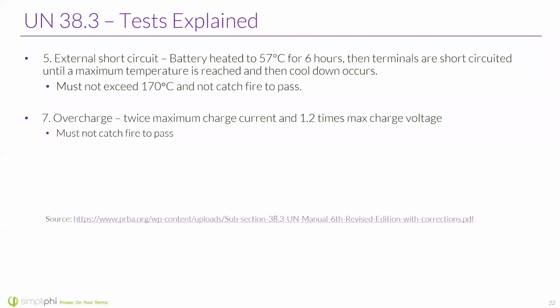And the last one, overcharge: twice maximum charge current. So we allow for 37.5, they use twice that, and 1.25 times max charge voltage, and it must not catch fire. Again, this is not saying that you can do these things to the battery and it maintains its warranty. We've just gone through this testing to make sure safety really is above all with these batteries.